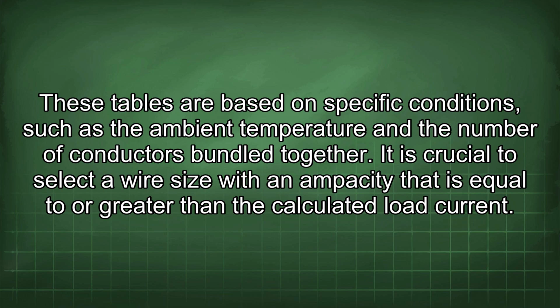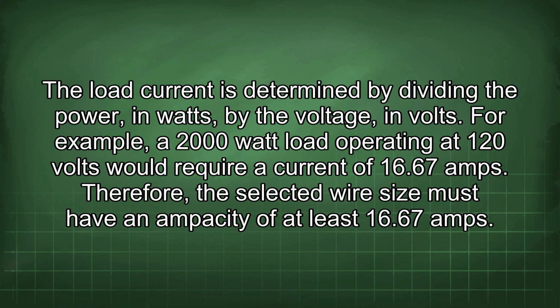These tables are based on specific conditions, such as the ambient temperature and the number of conductors bundled together. It is crucial to select a wire size with an ampacity that is equal to or greater than the calculated load current. The load current is determined by dividing the power, in watts, by the voltage, in volts. For example, a 2000 watt load operating at 120 volts would require a current of 16.67 amps. Therefore, the selected wire size must have an ampacity of at least 16.67 amps.